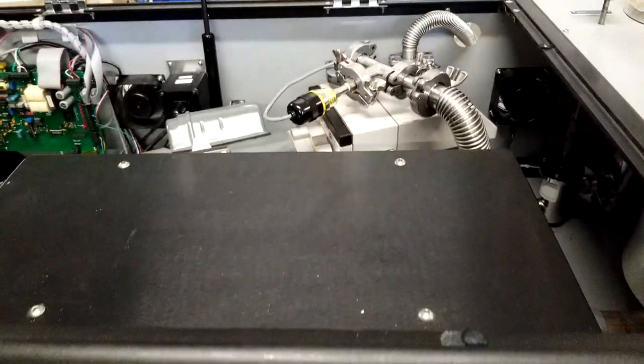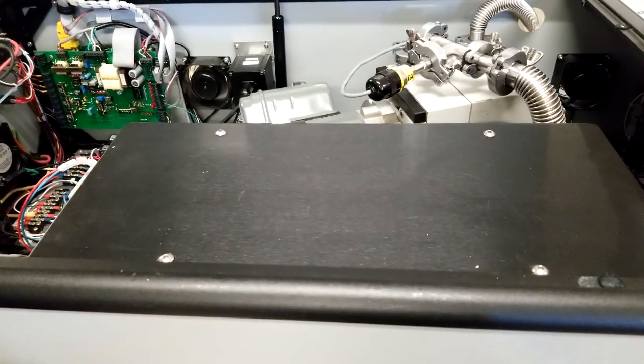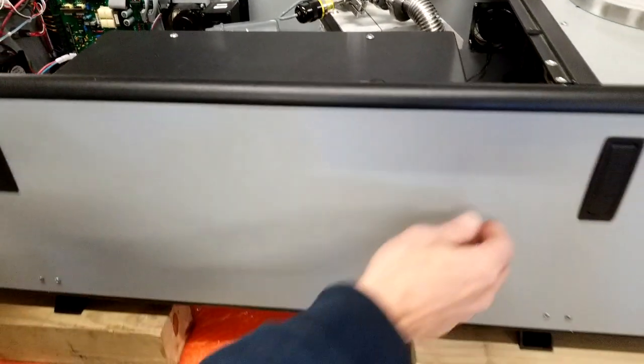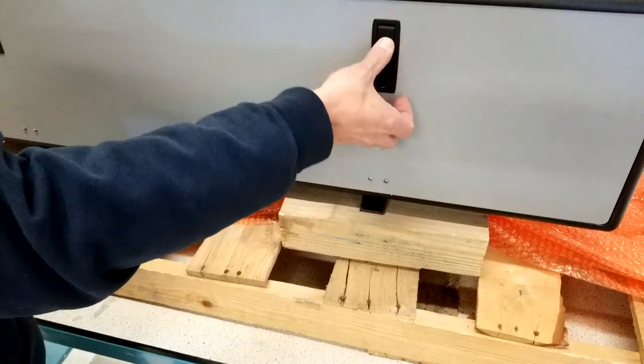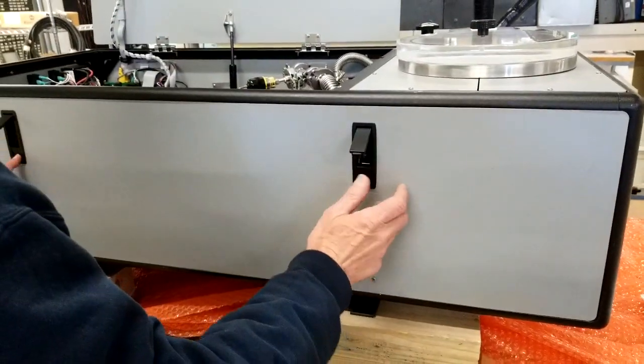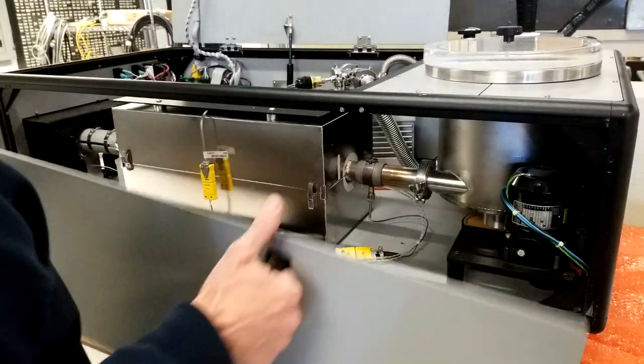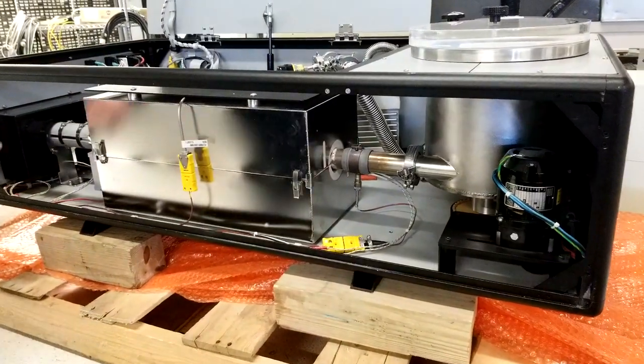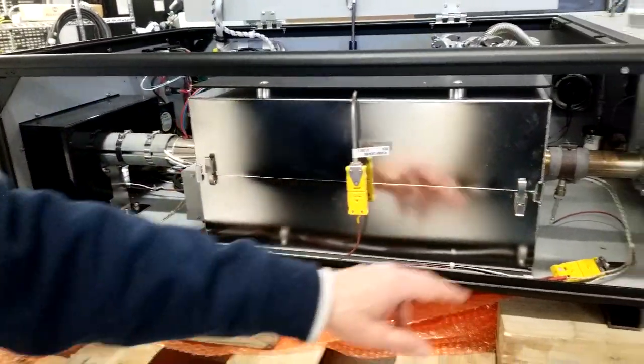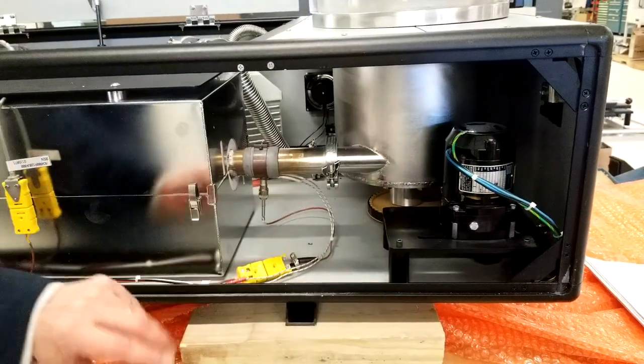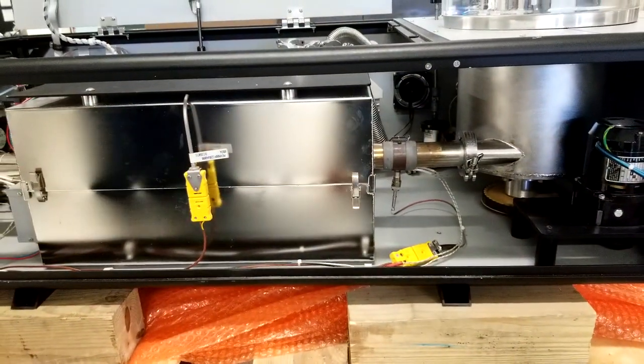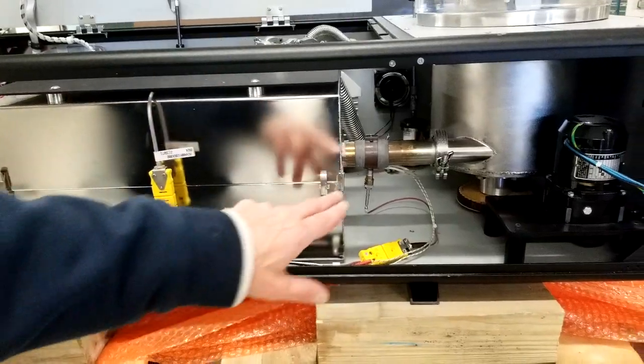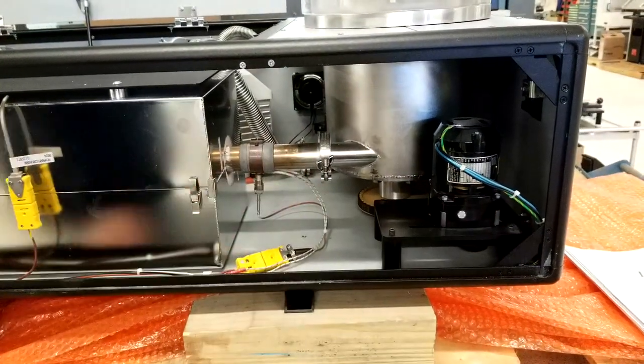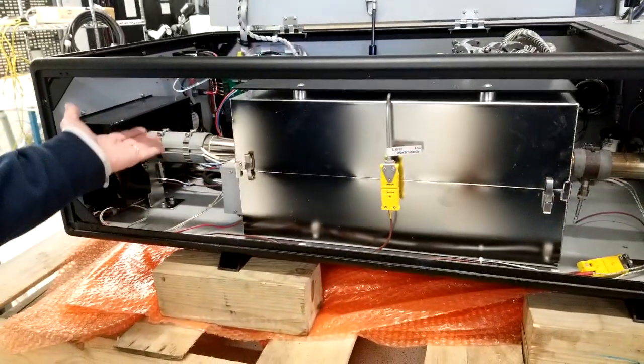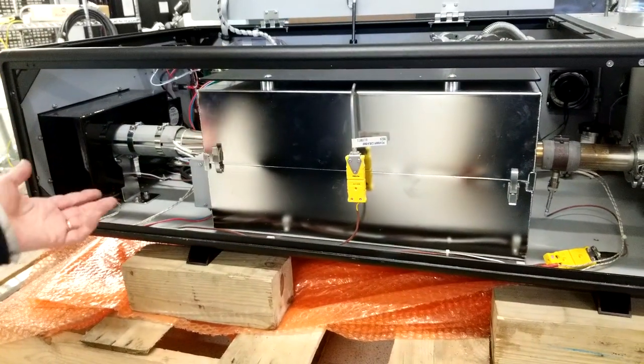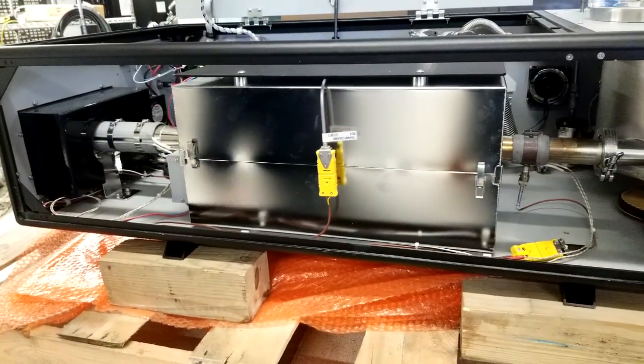Looking down, here's your vaporizer chamber. Well, actually, I can open the front door here. Just open this up real quick, point out a few things, and I'll close it up and run across. Okay, over here to your left, that's your vaporizer heater, your post pyrolysis heater, and your pyrolysis tube right here. So this is at 650. This is at around 220, and then we're going to control our vaporizer. So this will rise up to the program we have right now, rise up to about 130.